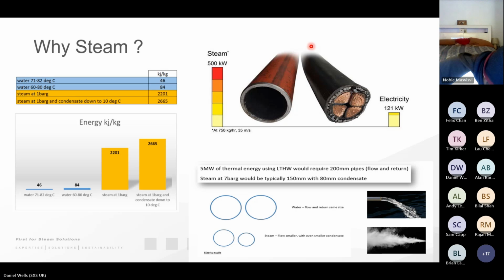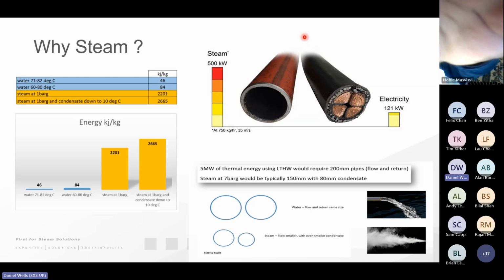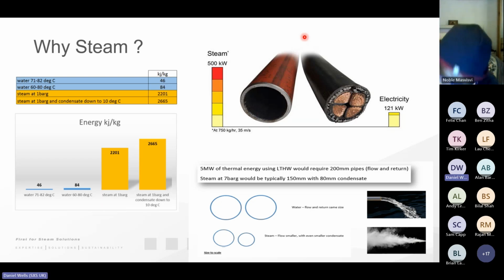But we also know that because there's more energy in gas and therefore in steam that is produced traditionally, we're going to have to size those heat exchangers on that maximum instantaneous demand for thermal energy. So I'm going to use the example of a hospital here. If we were producing hot water from steam in a hospital, that hot water will be available very, very quickly. The only way we could guarantee that that same mass of hot water would be available if we were producing it via an air source heat pump would be to ensure that we'd sized those heat pumps on that maximum instantaneous peak demand at 9 o'clock in the morning. That may mean that we need a significant overhaul and upgrade of the electrical infrastructure, which may mean that those heat pumps are no longer viable. So, as I mentioned, in many cases, heat pumps are absolutely the right thing to consider.